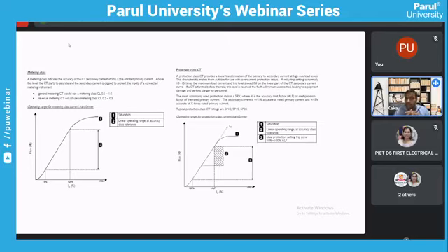So the most common practice is to use 5PX, where, as I said, that X is the accuracy limit factor. Again, this accuracy limit factor is derived further in calculation based on the burden rating of the CTs as well. So we need to check that my CT won't get saturated under normal conditions of the system short circuit, and that it's sufficient to perform the protection operation without getting saturated or falling into the saturation zone.